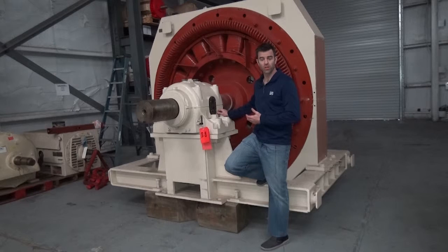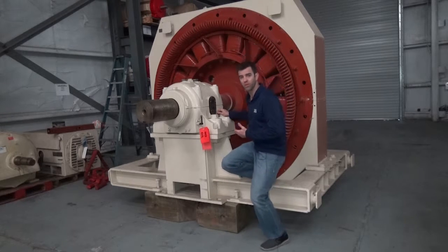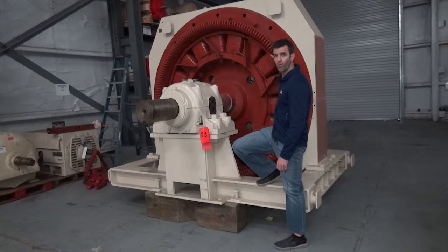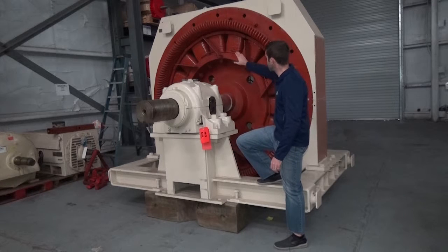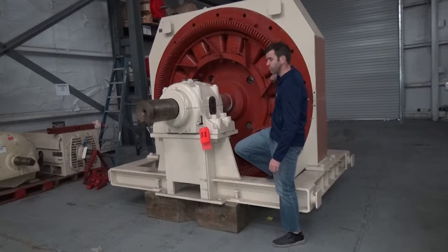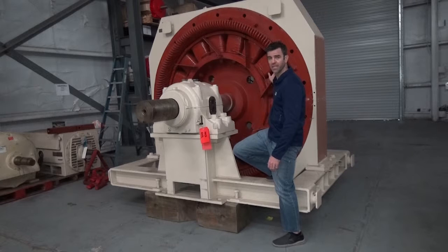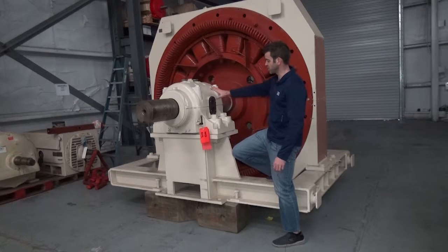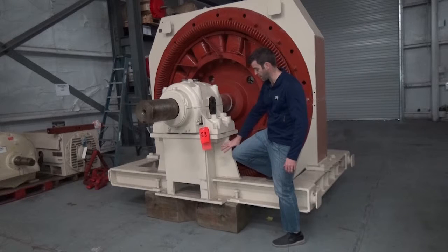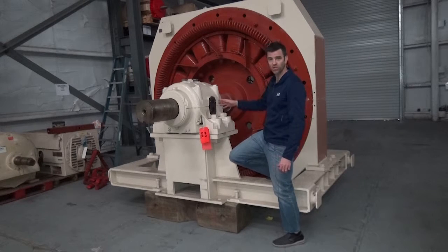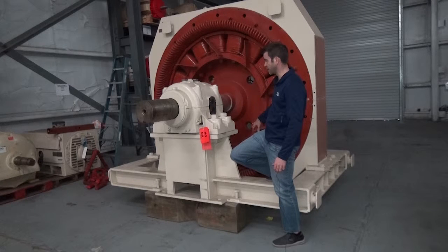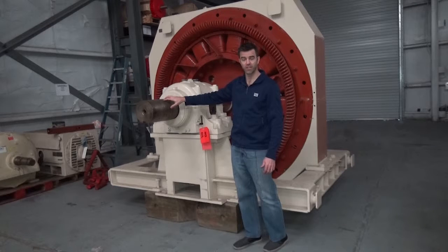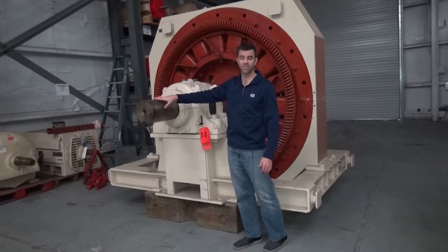Here we have a much larger synchronous motor, and we can talk about some of the components. You can see here that we have form-wound stator coils, which are very typical for medium and high voltage applications. You can see the individual poles here, and we can see the blower fan. This is a very low-speed machine, so the blowers are very rudimentary, in this case just flat steel plates. This machine has a pedestal bearing, which is mounted on its own pedestal and on a base, and that's in contrast to a bracket bearing, which would be mounted on a bracket to the machine. This is clearly the drive end of this motor because we can see the shaft protruding, and this would have a coupling or other device to connect it to the driven equipment.